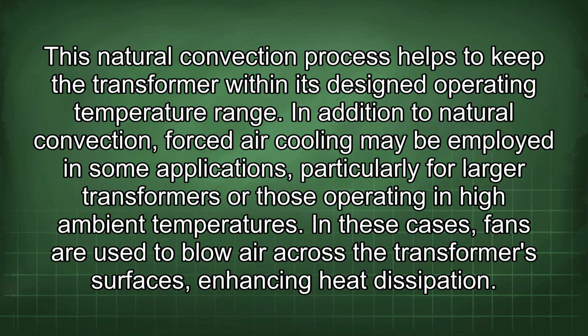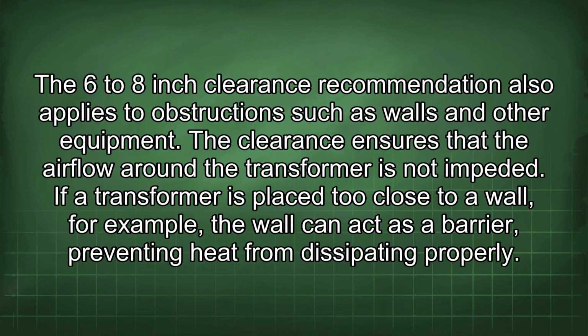In addition to natural convection, forced air cooling may be employed in some applications, particularly for larger transformers or those operating in high ambient temperatures. In these cases, fans are used to blow air across the transformer's surfaces, enhancing heat dissipation. The 6 to 8 inch clearance recommendation also applies to obstructions such as walls and other equipment. The clearance ensures that the airflow around the transformer is not impeded.